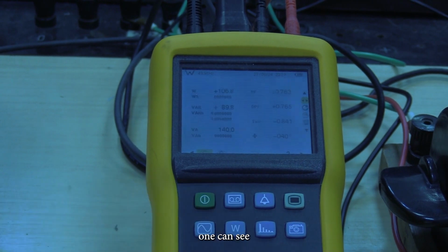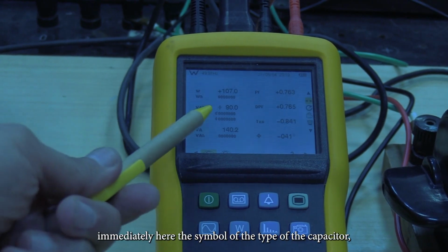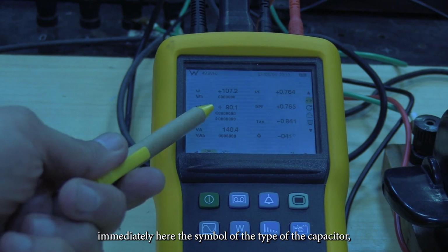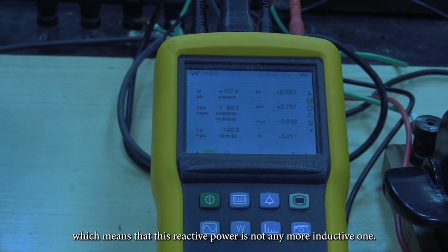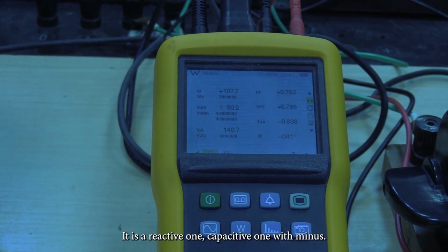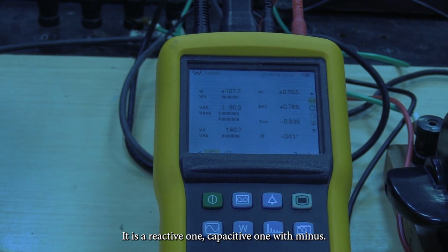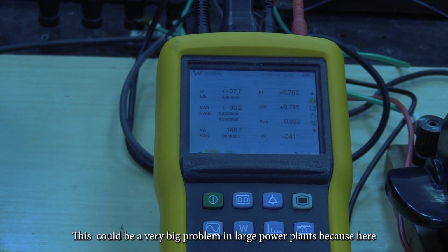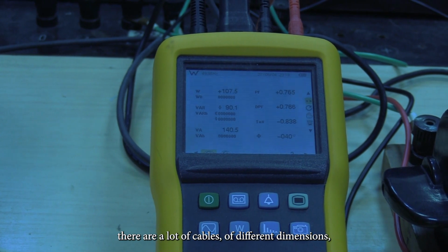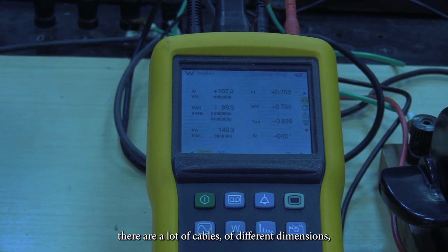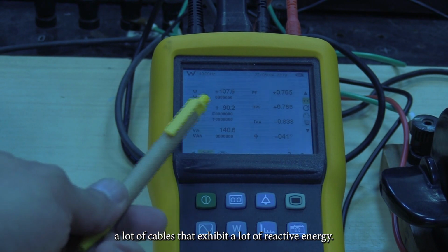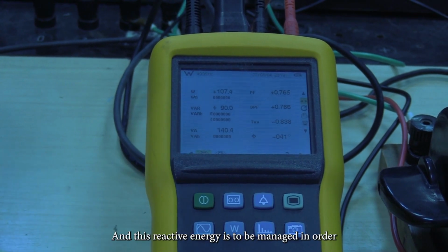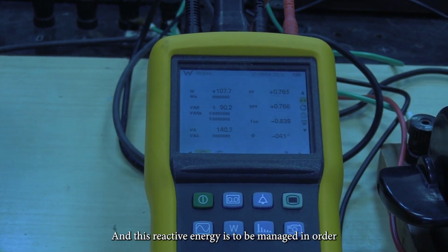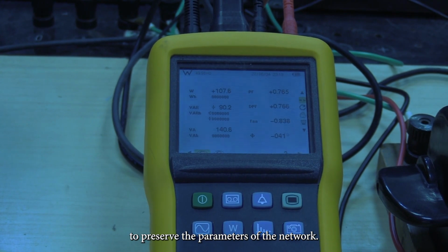One can notice also the power, and we can see immediately here the symbol, the type of the capacitor, which means that this reactive power is not anymore an inductive one, it is a capacitive one, with minus. This could be a very big problem in large power plants, because there are a lot of cables of different dimensions, a lot of cables that exhibit a lot of reactive energy, and this reactive energy is to be managed in order to preserve the parameters of the network.